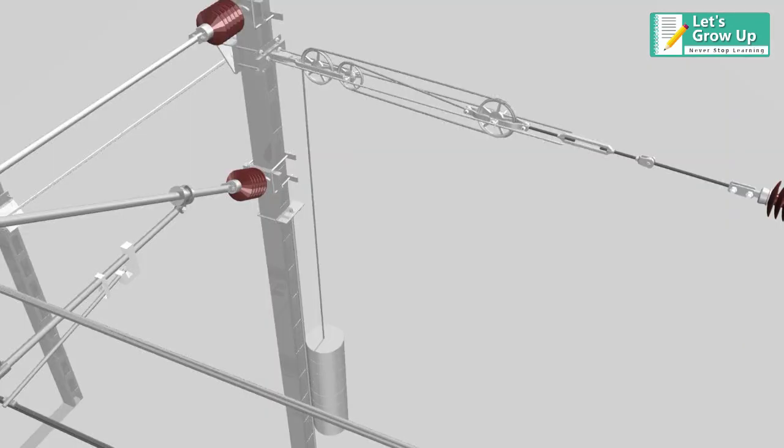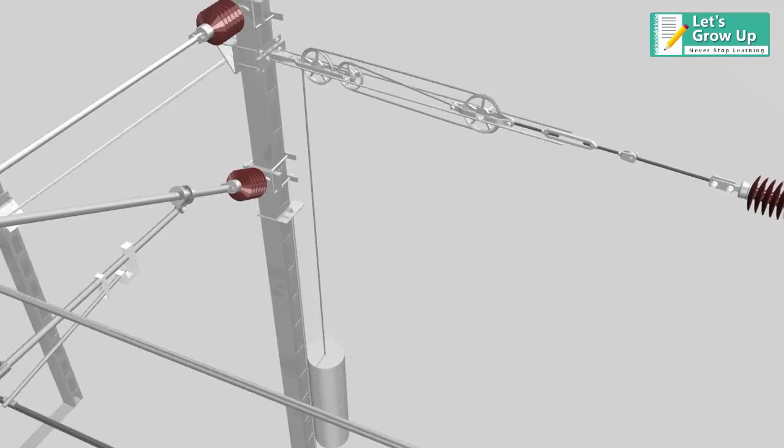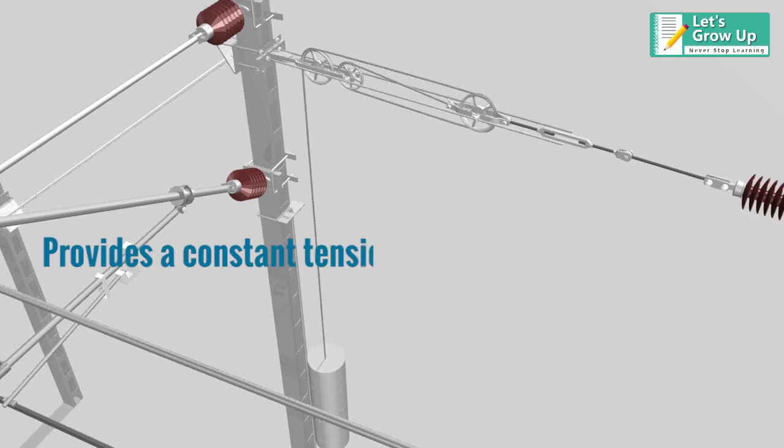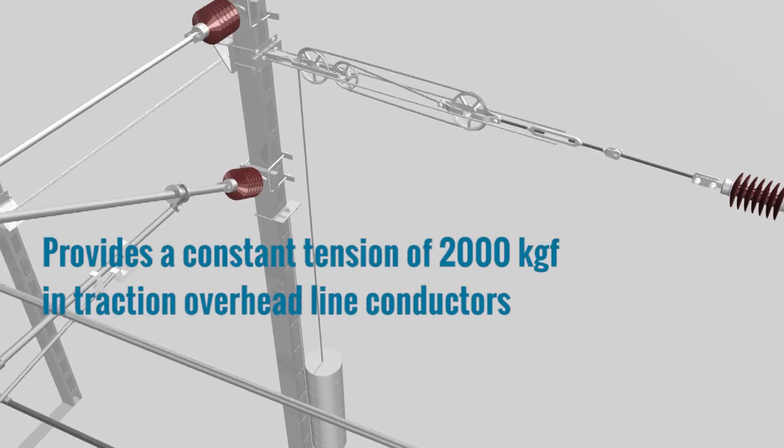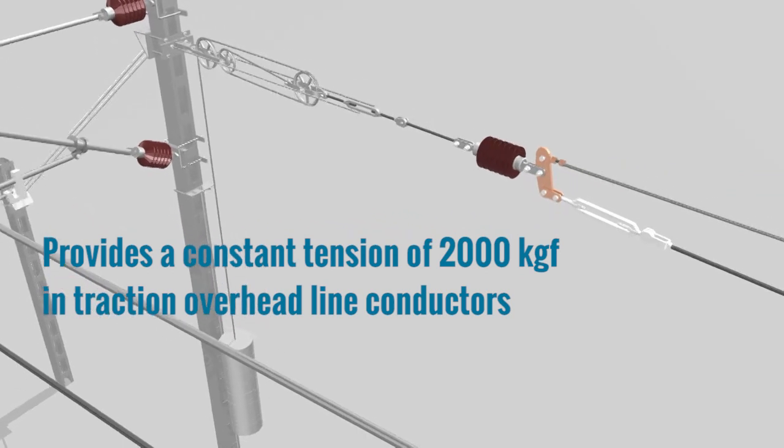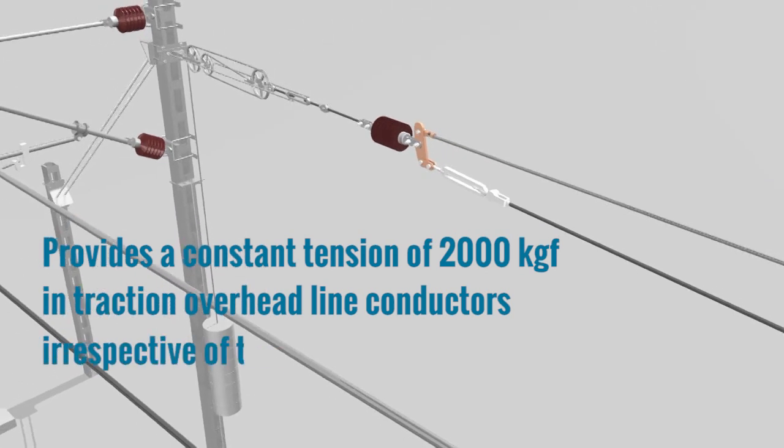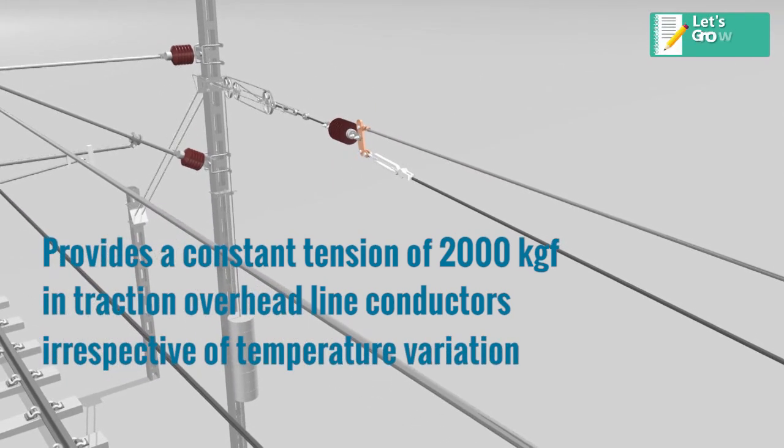It provides a mechanism to apply a mechanical load in catenaries and provides a constant tension of 2000 kg force in traction overhead line conductors, irrespective of temperature variation.